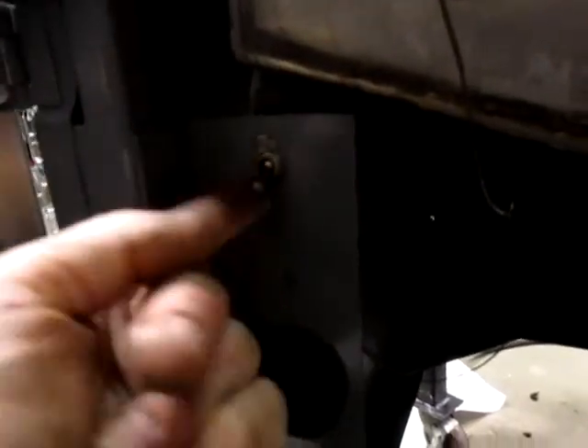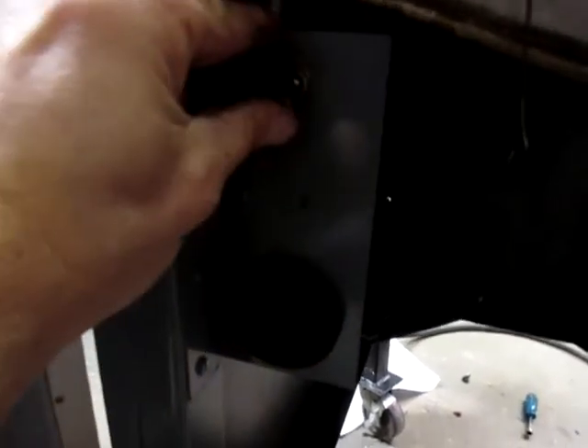Here's the thermostat and power switch, turn it off and on. The reason you don't hear the contactor clicking in and out is because the thermostat's turned down. You turn that up, turn it on, and now listen - you'll hear the contactor click in and out. Let me show you that.